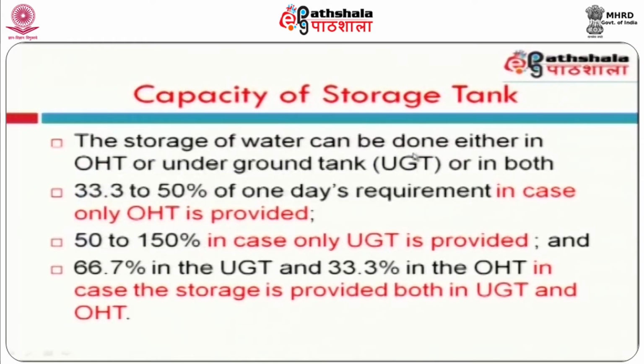So, the storage, as I said, can be done either in the underground tank or in the overhead tank or both the tanks. 33.3 to 50% of one day's requirement in case only OHT is provided. If you do not have an underground tank, the water coming from the municipal water supply is directly taken to the storage reservoir and then distributed. In such a case, the storage requirement is only 33.33%, that is 1/3 of the daily requirement.